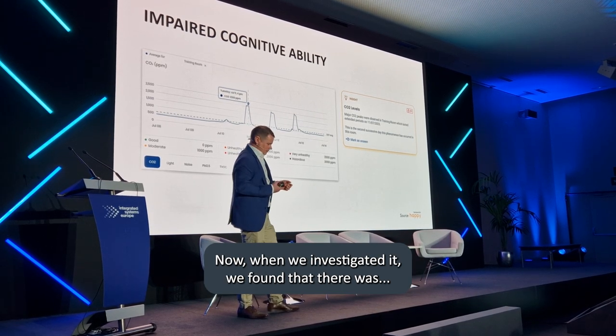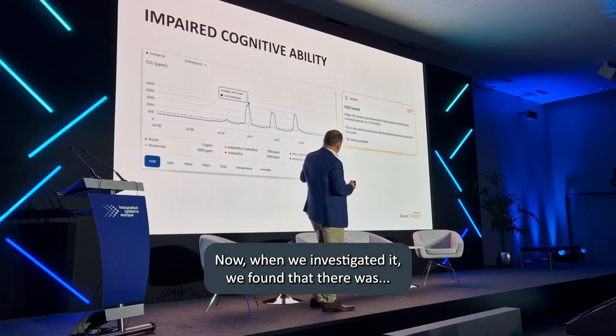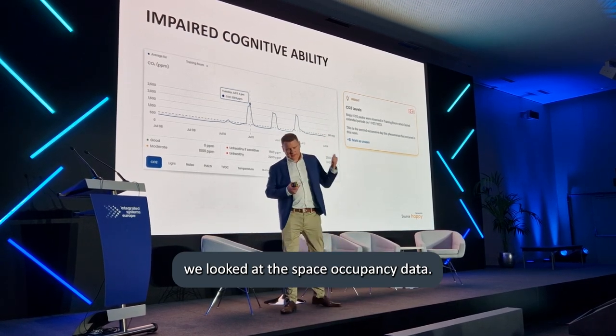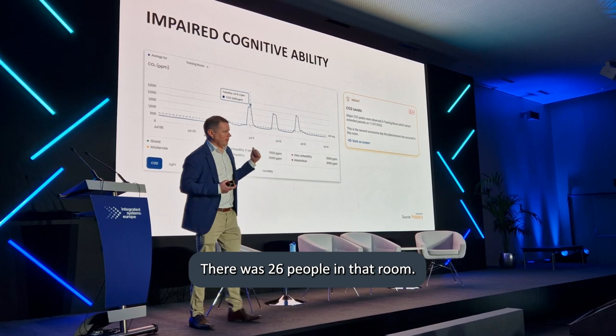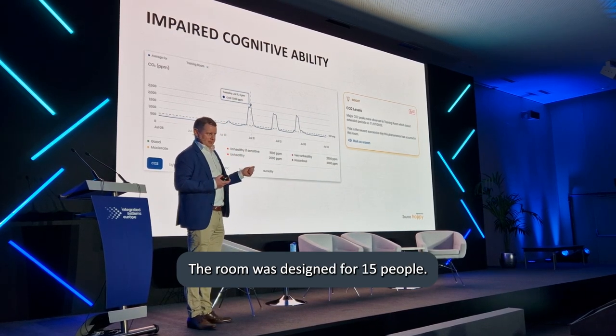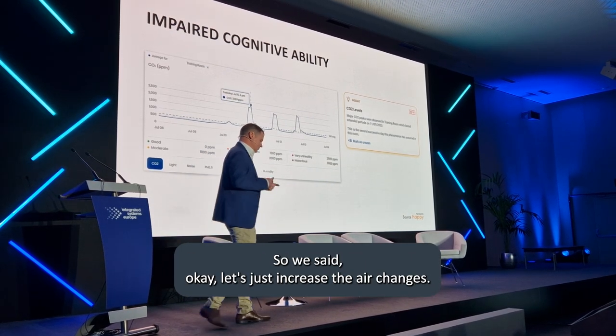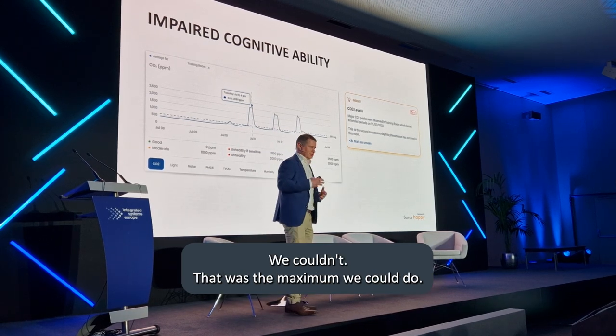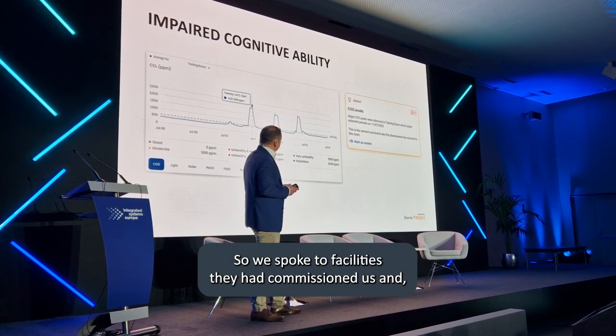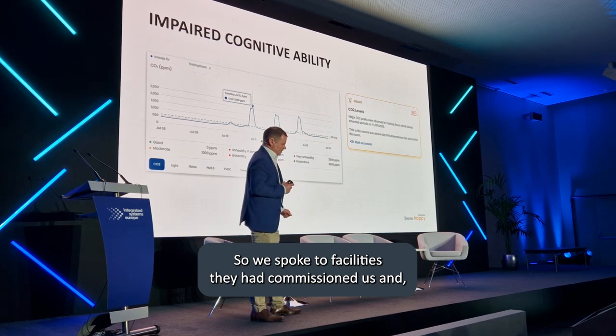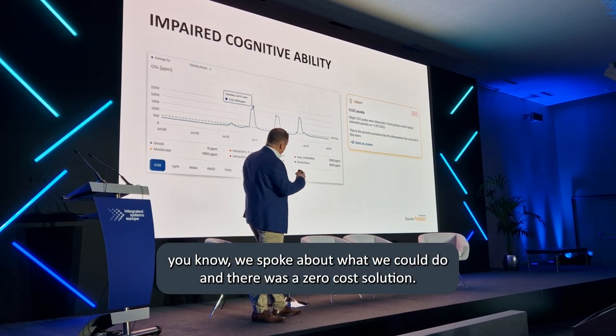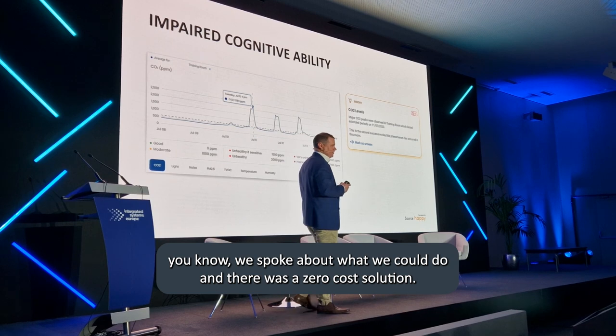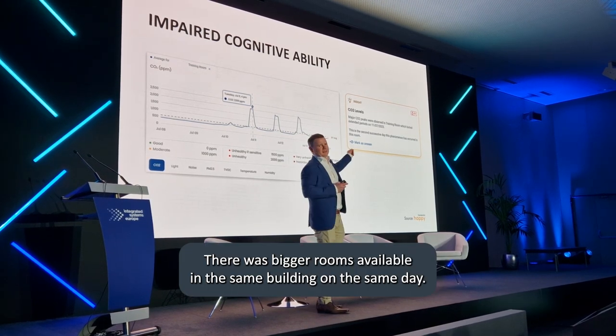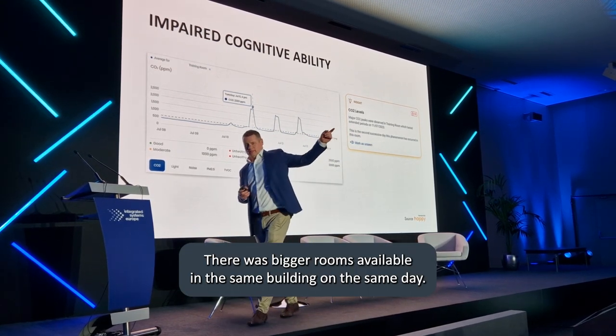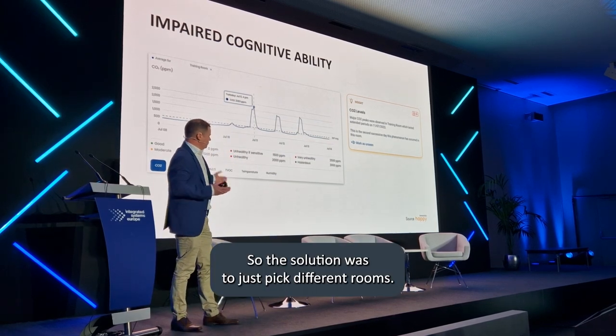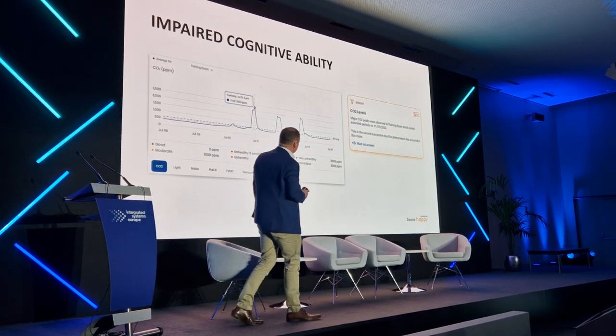When we investigated, we looked at the space occupancy data and found there was 26 people in that room, which was designed for 15. So we said, let's just increase the air changes, but we couldn't, that was the maximum we could do. We spoke to facilities, who had commissioned us, about what we could do, and there was a zero cost solution: there were bigger rooms available in the same building on the same day. So the solution was just to pick different rooms.